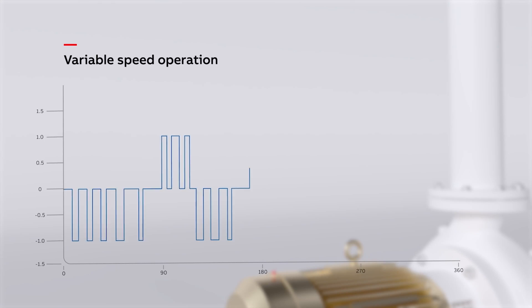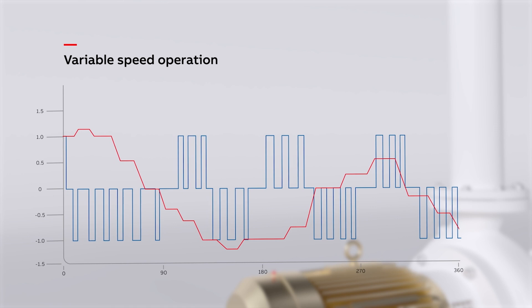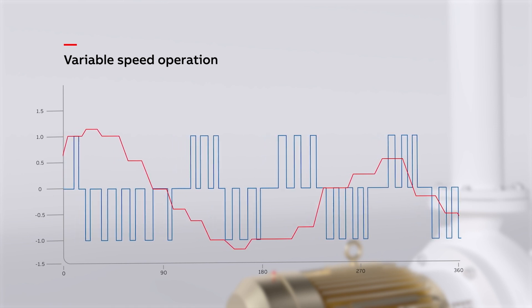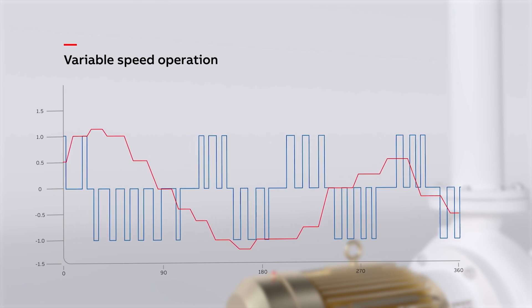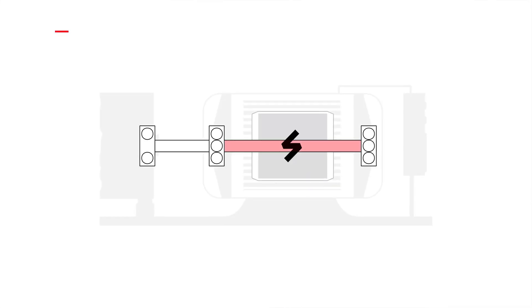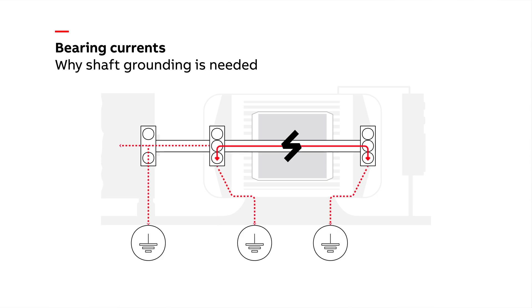When motors are controlled by a VFD, the power is converted to a series of pulses that emulate the sine wave, but is not exact. The result is an imbalance known as common mode voltage. The common mode voltage builds up across the bearings due to the dielectric effect of the bearing grease and will eventually discharge through the bearings to ground. Unfortunately, common mode voltage cannot be eliminated, but it can be reduced.